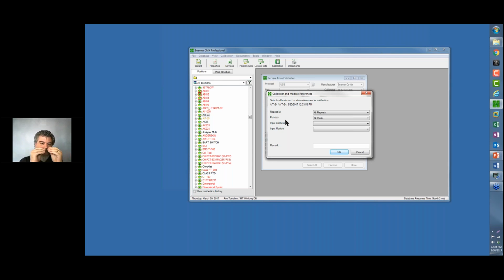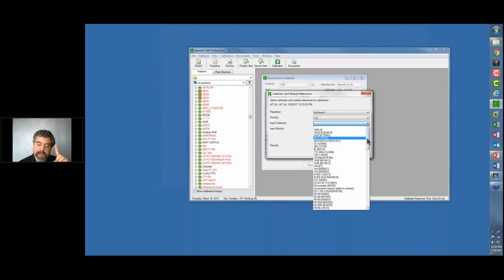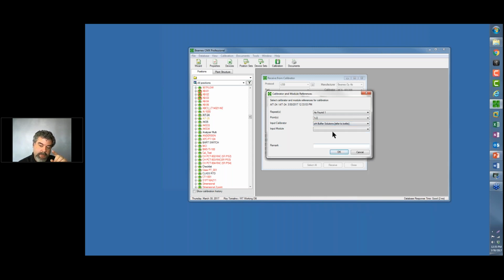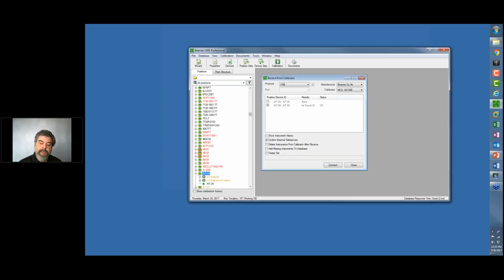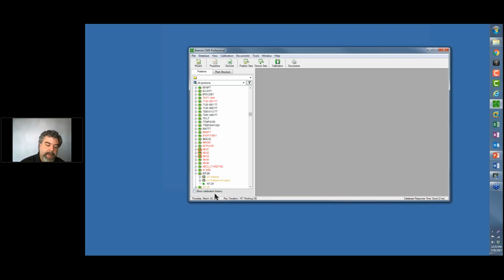Now this is where I connect those dots and say I used this buffer solution for number 4 of this lot number, etc. So for the repeats, let me go to as found 1. Point number 1 was my pH standard, which is down here, and I used this one with this serial number, or this was the lot number off the bottle. Now for point number 2, I'm still using this pH standard, but I used this pH 10 solution with this lot number. Now I'll hit OK, and it brought it over. So now we'll find it.